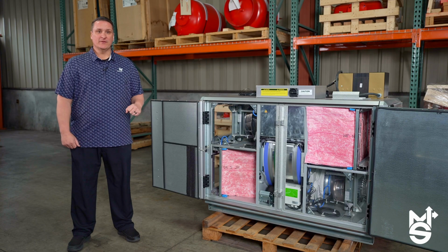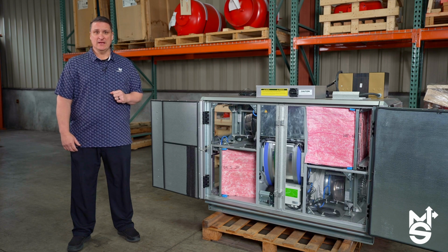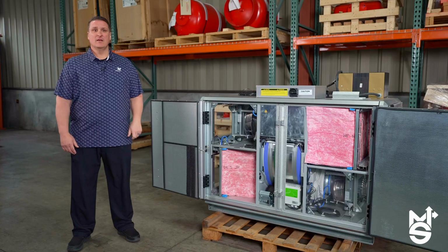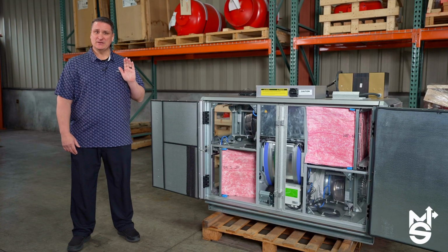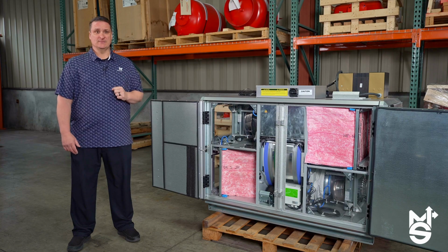What are typical defrost control sequence solutions in the marketplace, and how does Swegon provide their defrost solution? Typical defrost management in most sequences is controlled by reading the entering air temperature or the exhaust air temperature. But frosting occurs at a combination of both temperature and humidity. Managing defrost from a temperature-only set point is extremely energy inefficient. Swegon has put out a terrific white paper on defrost management.